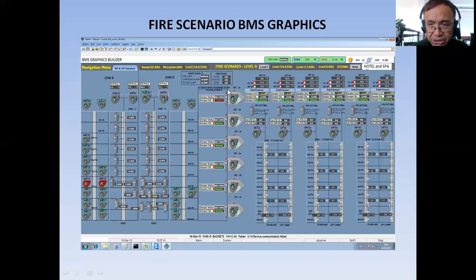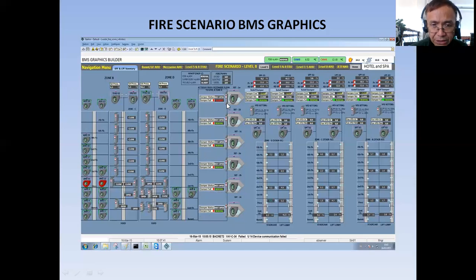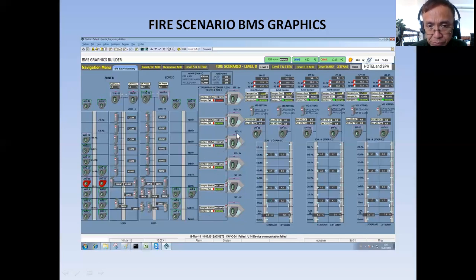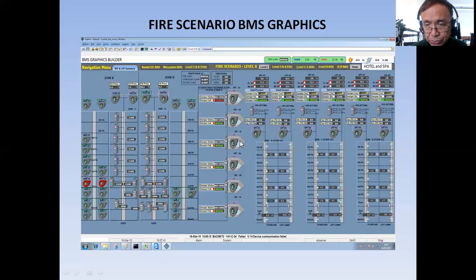These points are related to staircase pressurization. I also have here smoke extraction fans — I have six smoke extraction fans because in that project we have a dome. All the smoke will be pushed into the dome and it will be extracted by all these smoke dampers and extraction fans. Each fan also has a damper. During a normal scenario with no fire, all these dampers are closed, to prevent hot air from entering the building and to prevent condensation.